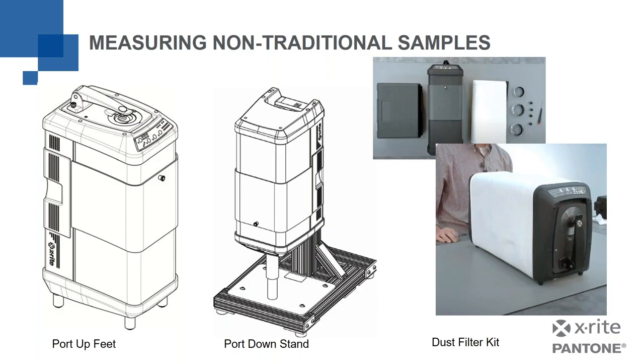Doesn't stop it 100% completely, but it slows it down greatly, so that you're talking about maybe once a year you have to have the instrument cleaned, rather than in a very dusty environment. We've seen instruments fail in a matter of weeks. And so this does a very, very good job of allowing you to take those measurements.